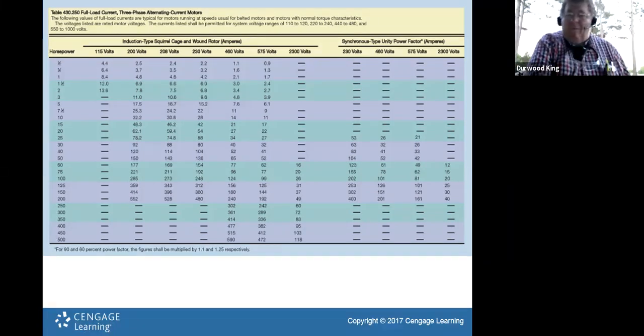350. Pick a big one. So you've got a 350 horsepower motor right there. And let's come across to the voltage. What voltage do you want to run at? You want to stick it at 460? Yeah. Sounds pretty common. Now it is. That's 414 amps.